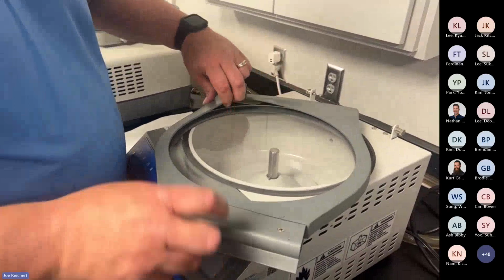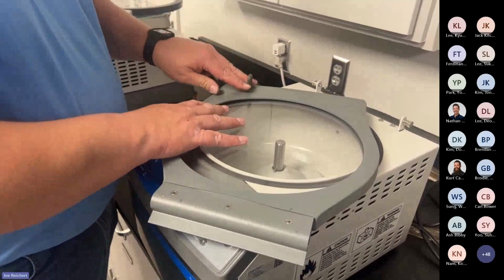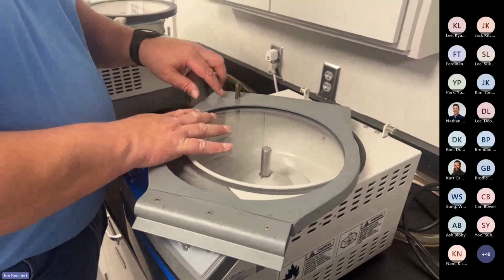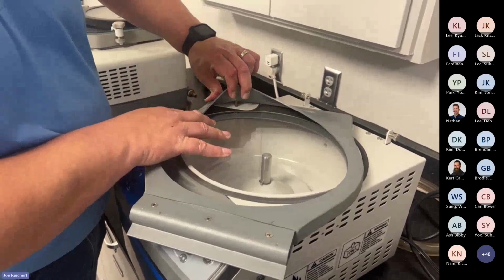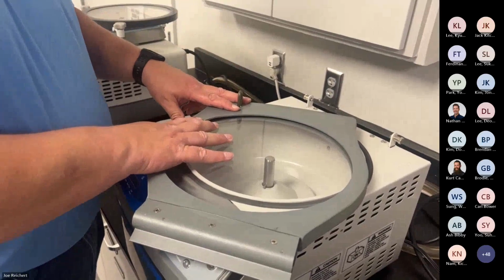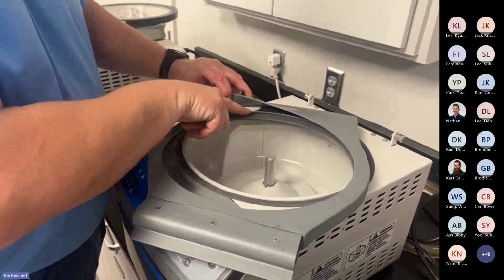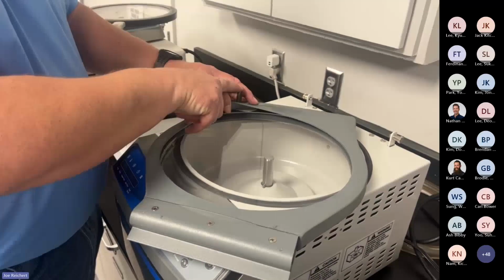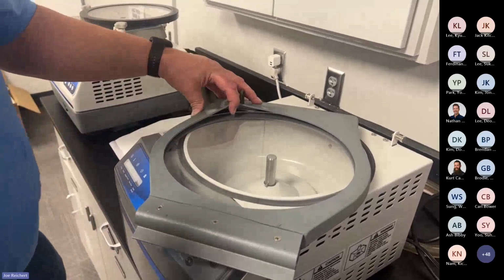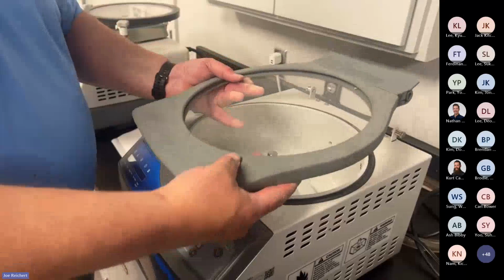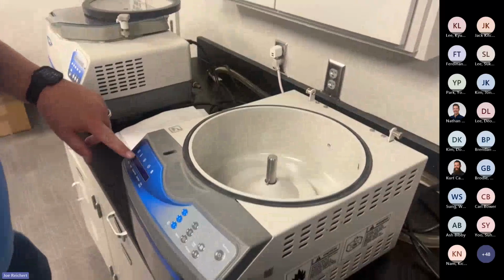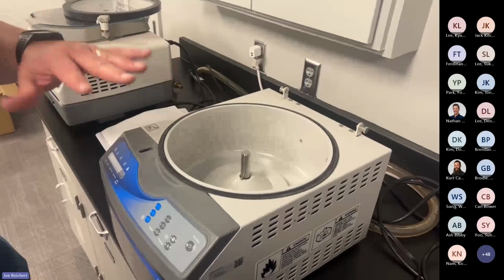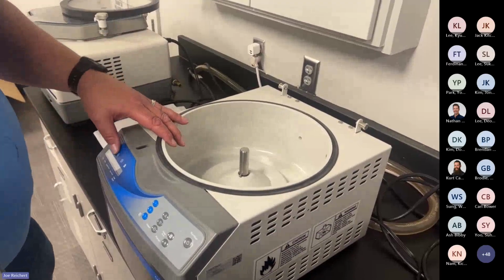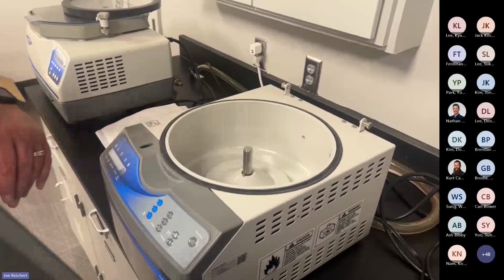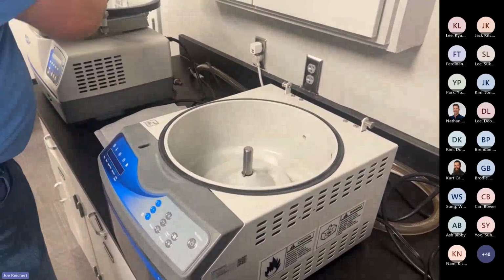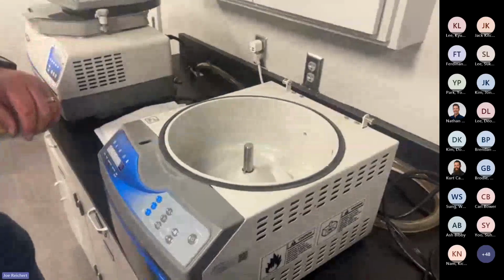But we have also seen a few issues on the glass lids. On the glass lids, this U-shaped piece is welded to a plate. It doesn't go through the acrylic or through the lid like it does on an acrylic unit. We've seen that spacer overlap the plate that the U piece is welded to. And if it overlaps it, it's just by the thickness of the metal, but it might hold the lid up high enough that you start getting closed lid signals. It's kind of intermittent because it's really close to having that button pushed all the way down. So sometimes it'll work, sometimes it won't. If it's a glass lid, check out the lid. That's probably where your issue is going to be. Make sure that spacer is not overlapping the plate.